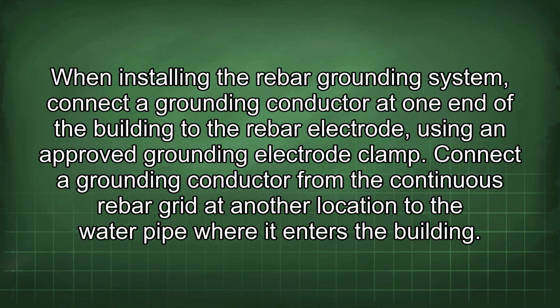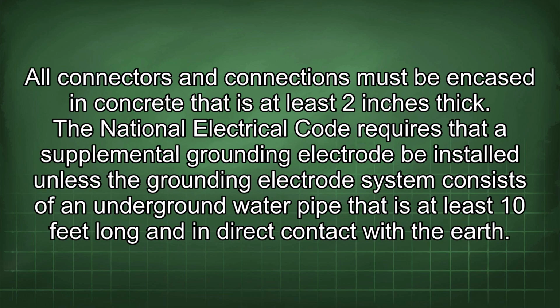When installing the rebar grounding system, connect a grounding conductor at one end of the building to the rebar electrode, using an approved grounding electrode clamp. Connect a grounding conductor from the continuous rebar grid at another location to the water pipe where it enters the building. All connectors and connections must be encased in concrete that is at least 2 inches thick.